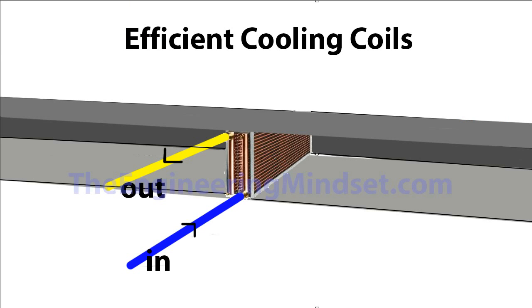Another important step for chilled water cooling coils is to check that the chilled water is entering through the bottom and rising up against gravity. This gives it more chance to become turbulent, give up some of that thermal energy, and make its way out of the top. If it has been piped the other way — chilled water entering through the top and leaving through the bottom — piping it the correct way around will probably give you anywhere between five and fifteen percent increase in effectiveness.